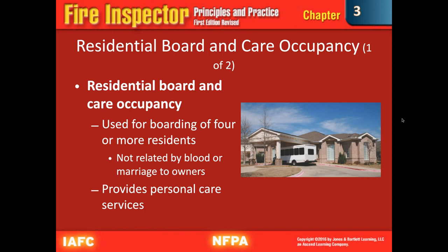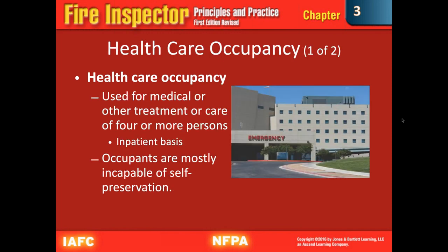The inspector must be able to distinguish between personal care and health care. If nursing care is provided, then the facility is healthcare occupancy. If there is no nursing, and it's just, say, CNAs, people to help them with their day-to-day routine but not medical care, then that is personal care. Inspections for these focus on the capability to evacuate residents in the event of an emergency.